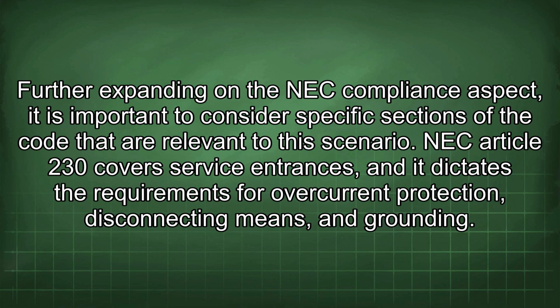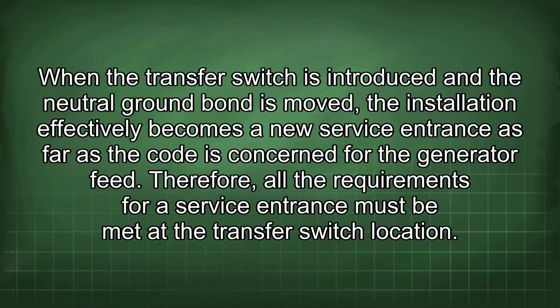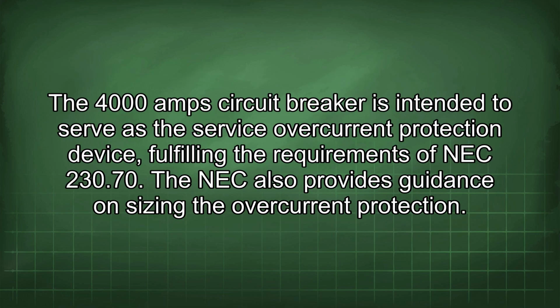Further expanding on the NEC compliance aspect, it is important to consider specific sections of the code that are relevant to the scenario. NEC Article 230 covers service entrances, and it dictates the requirements for overcurrent protection, disconnecting means, and grounding. When the transfer switch is introduced and the neutral ground bond is moved, the installation effectively becomes a new service entrance as far as the code is concerned for the generator feed. Therefore, all the requirements for service entrance must be met at the transfer switch location. The 4000 amp circuit breaker is intended to serve as the service overcurrent protection device, fulfilling the requirements of NEC 230.70. The NEC also provides guidance on sizing the overcurrent protection.